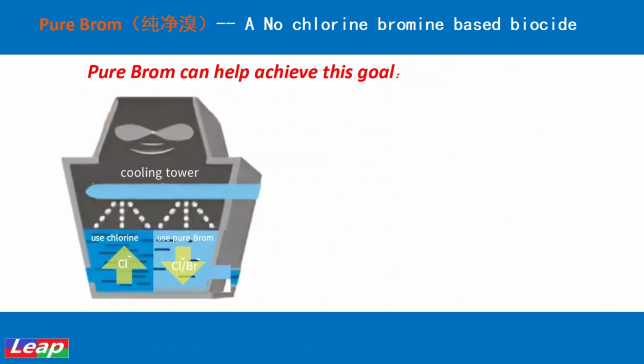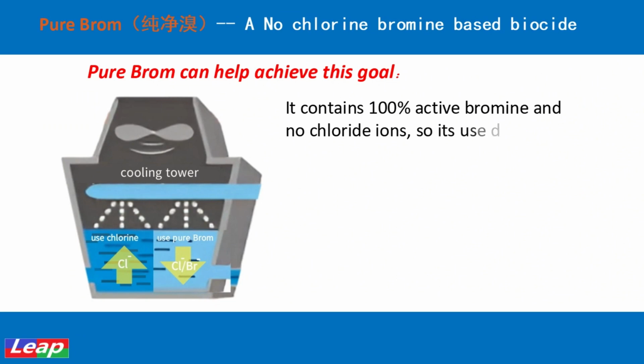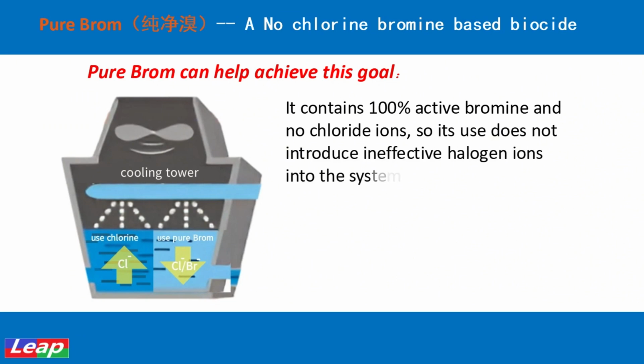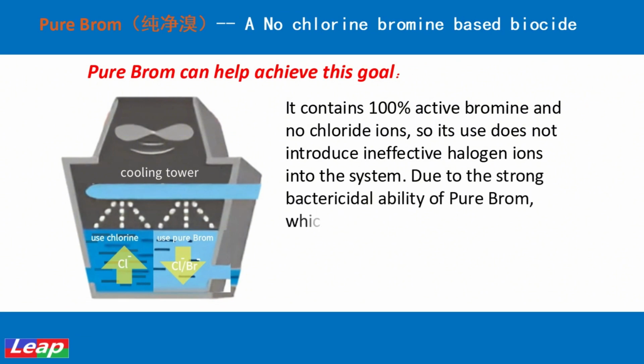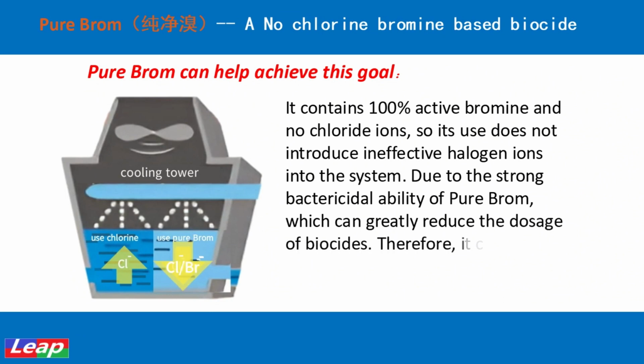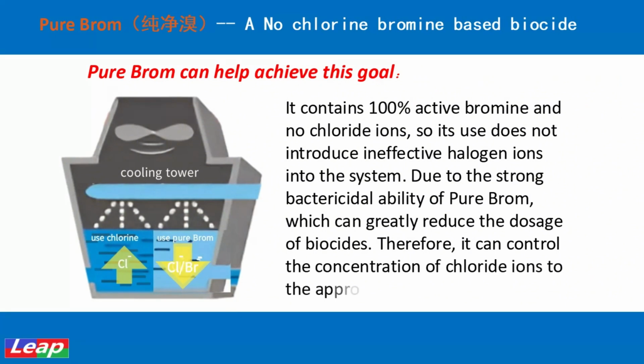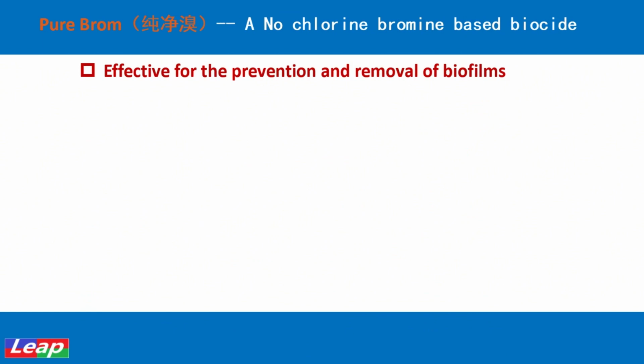Pure Brom can help achieve this goal. It contains 100% active bromine and no chloride ions, so its use does not introduce ineffective halogen ions into the system. Due to the strong bactericidal ability of Pure Brom, which can greatly reduce the dosage of biocides.